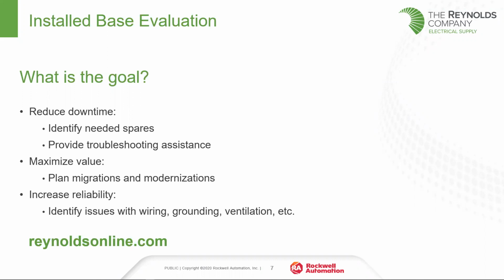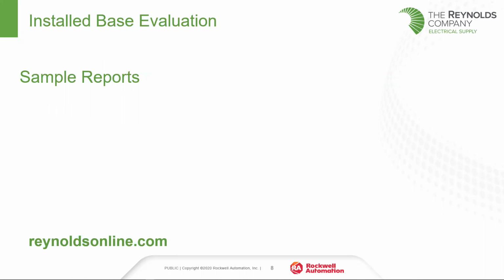And then there is a series of reports as well. That's just the general reliability. Are there wiring issues? Are there grounding issues? Do we have cabinets that look like they're left open and are now covered in concrete? I've seen that before. It wasn't pretty. The panel didn't last. Mike, you can go ahead to the next slide now.